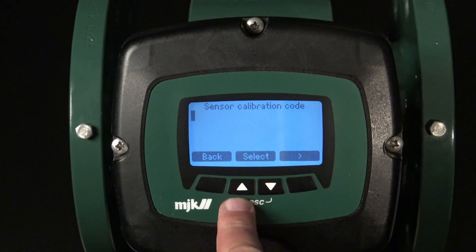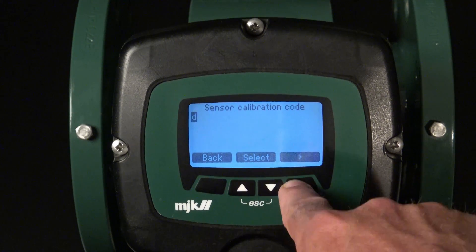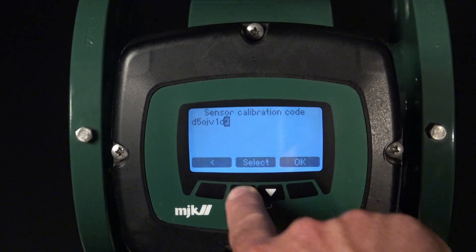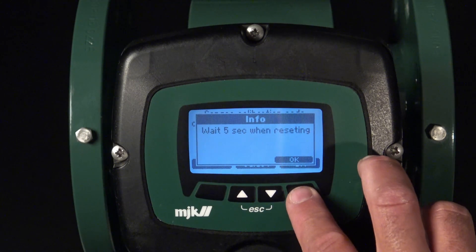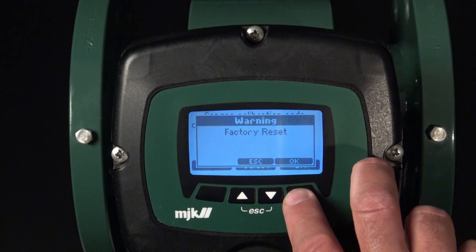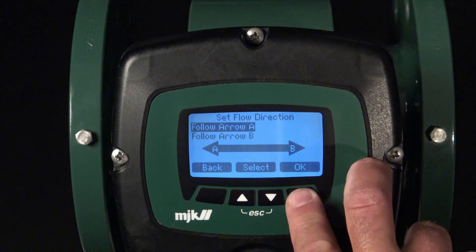Typing in the sensor code is done with the keypad. I will start to type in the first digit, which is a D. When all the digits have been typed in, you press OK. You wait five seconds and then press OK again. The unit will factory reset and set up the converter to the typed-in sensor code. Press OK again. We now have to determine the flow direction. In this case we will take the default flow direction, which is A. The MagFlux is now set up and is ready to measure.